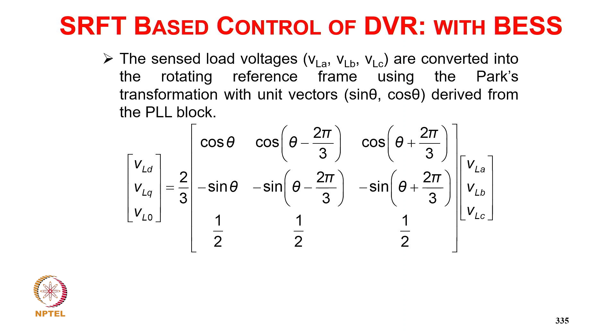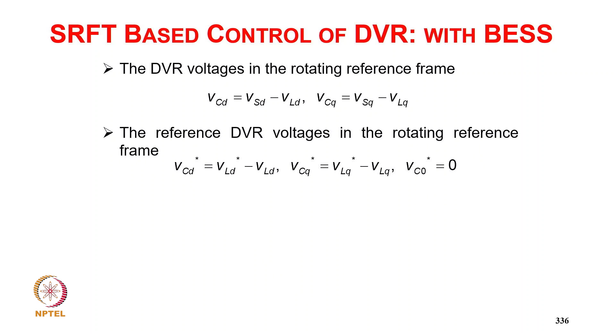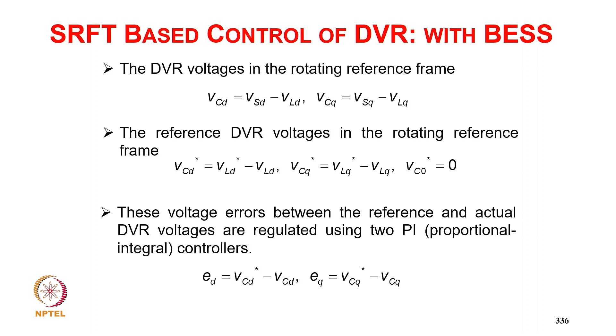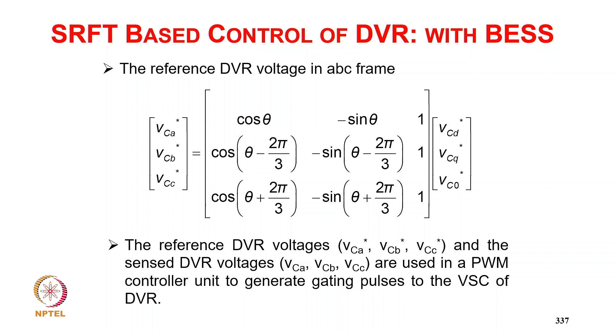Then we convert the actual quantities to DQ0 voltages, and then we calculate the compensating voltage VCd from VSd minus VLd. Similarly, VCq from VSq minus VLq, and we are able to get VCd star equal to VLd star minus VLd. Similarly for B phase and C phase, and these voltage errors between the reference and actual DVR voltages are regulated using PI controllers for Ed and Eq. And from the DQ components we get the ABC voltage for injection, so the DVR reference voltage and the sensed DVR voltage are used in the PWM controller to generate the gating signal for the VSC of the DVR.